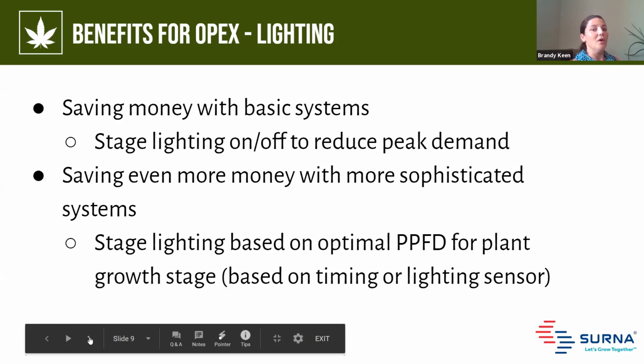A lot of times those demand charges can be outrageously high. We've seen people manage demand charges and cut their bill in half just by getting rid of those penalties for peak demand. That can be done with an entry-level system, assuming you've planned for that from the beginning and have enough relays to stage them.